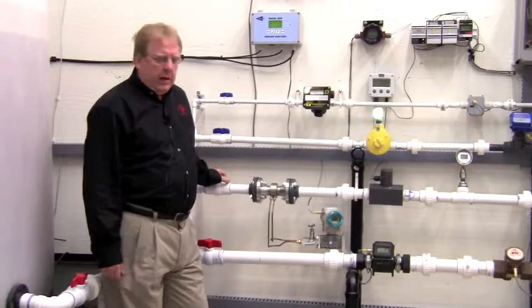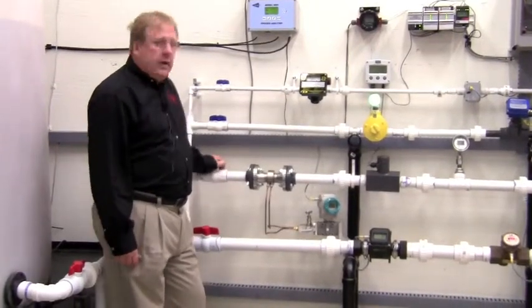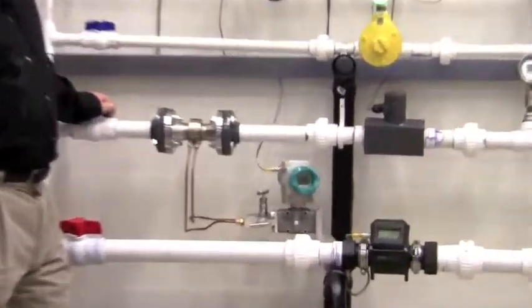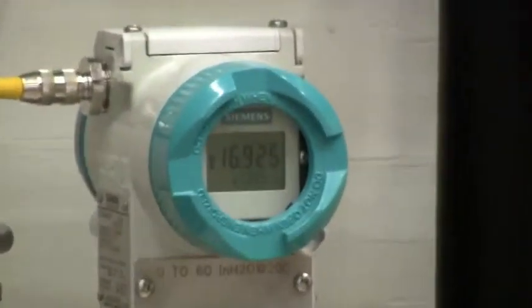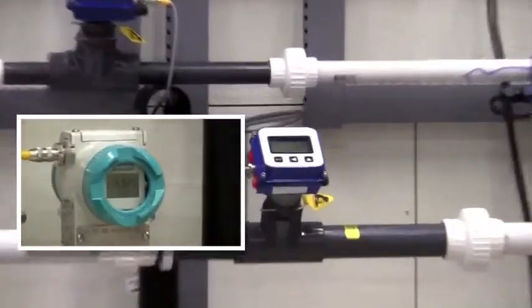Now, on our inch-and-a-half line, I'm going to throttle this valve back a little bit to decrease the flow, and as you can see, the reading on the DP transmitter and the Seametrics insertion meter are approximately the same.